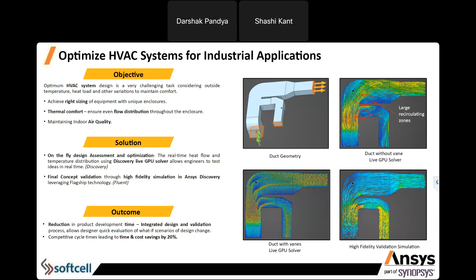At the top right, you will see large recirculation happening because of the airflow, and we can see pressure drop is there. On the bottom right, you'll see we made some changes in the HVAC and duct profile, and then this recirculation is not happening. So these changes make it very easy to achieve proper cooling for the data center.